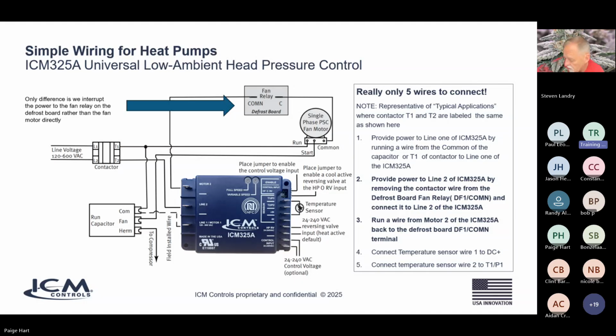That's going to condition the input at the HPRV to say that when we see a voltage there, we know that we're in cooling mode and we can go into variable speed mode. But when we don't see a voltage there, we know we're in heating mode and we will bypass this control and run the fan at full speed. Okay? Because in a heat pump, when you're in heating mode, you always want the fan at full speed. And so that's all we're looking at on the HPRV input: the input of the reversing valve, whether it's going to be heat active or cool active.